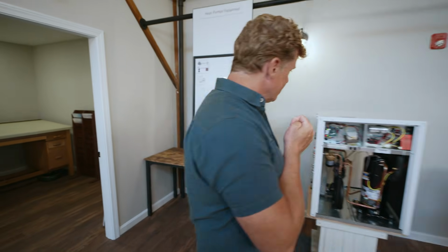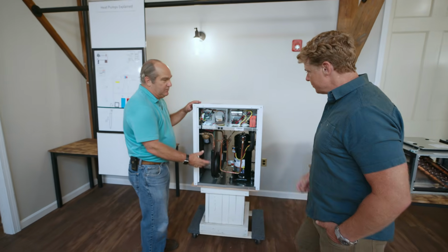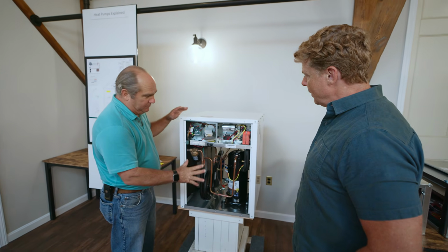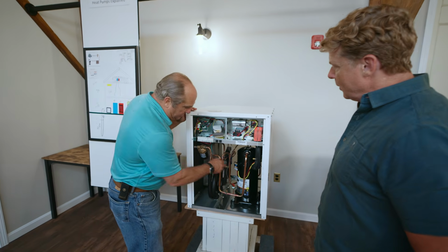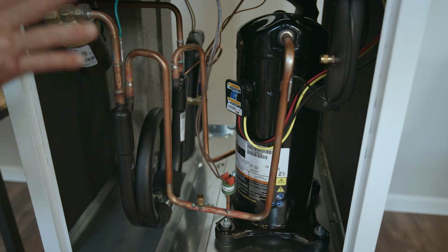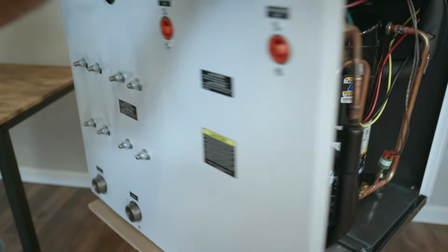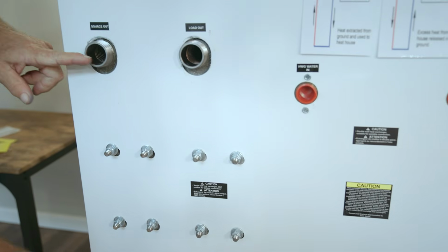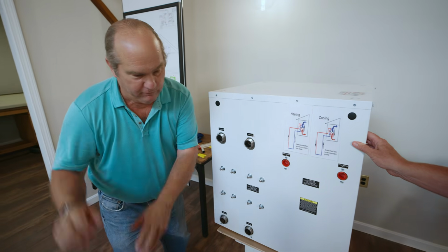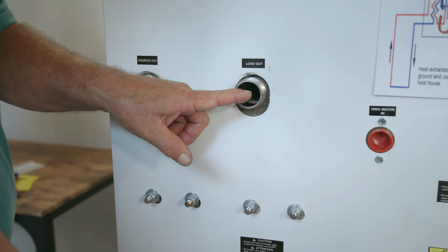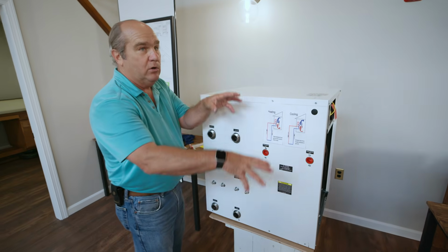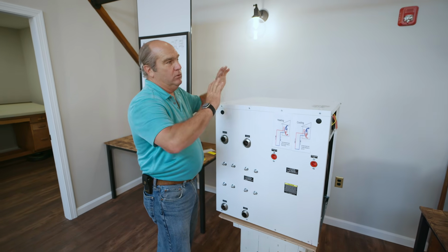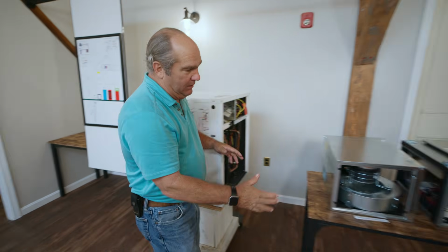And so the equipment we're looking at here is our lineup. Here's our geothermal heat pump. This is one of two that we'll have in the building. For simplicity, I just have the one. Compressor, expansion valve, reversing valve inside here. You can see there's tappings right here. This goes out to our wells, down, it could go 400 or 500 feet. This goes to our piping inside the building, to our load. Now that'll come up to the radiant, but also will go to air handlers.